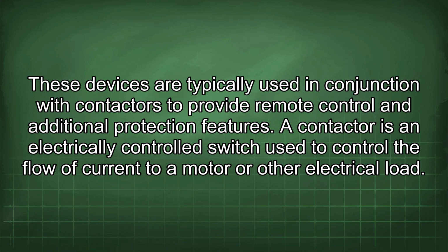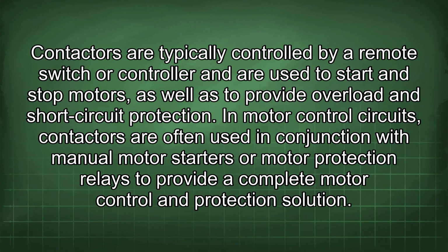A contactor is an electrically controlled switch used to control the flow of current to a motor or other electrical load. Contactors are typically controlled by a remote switch or controller and are used to start and stop motors, as well as to provide overload and short circuit protection. In motor control circuits, contactors are often used in conjunction with manual motor starters or motor protection relays to provide a complete motor control and protection solution.